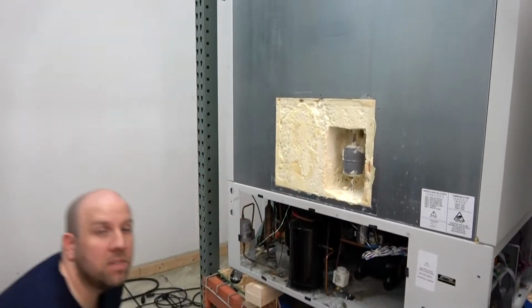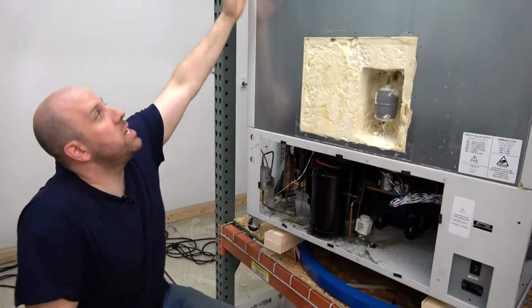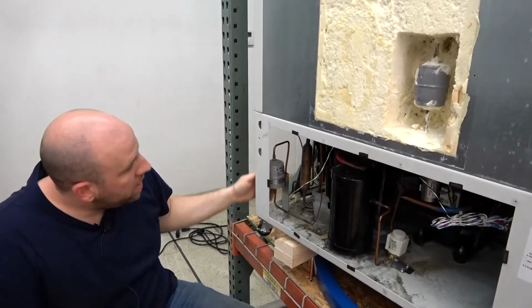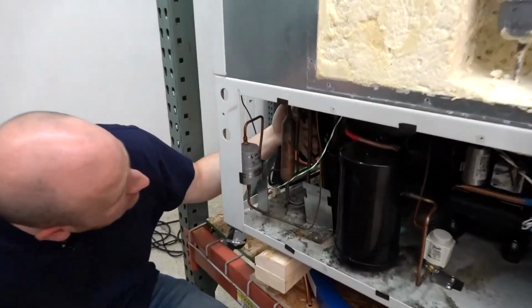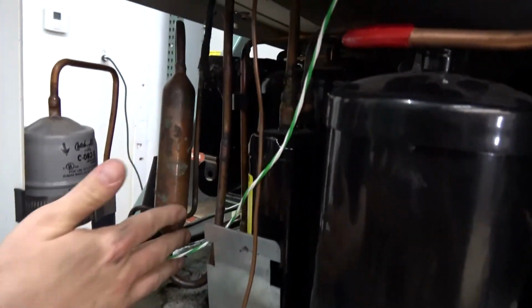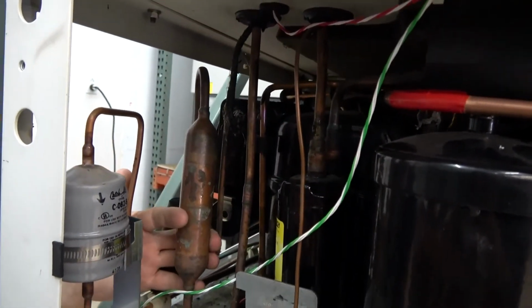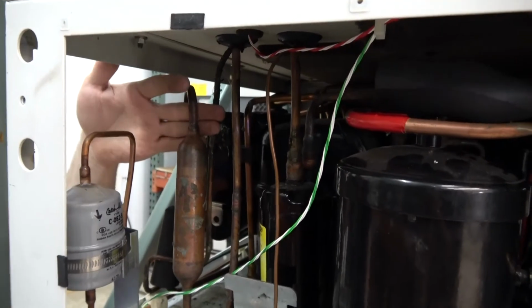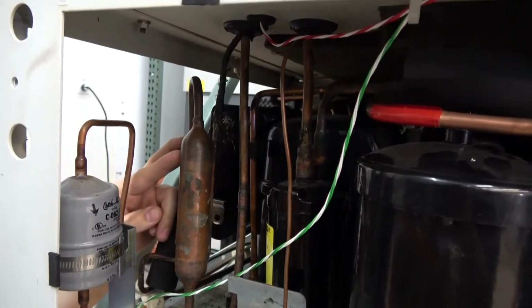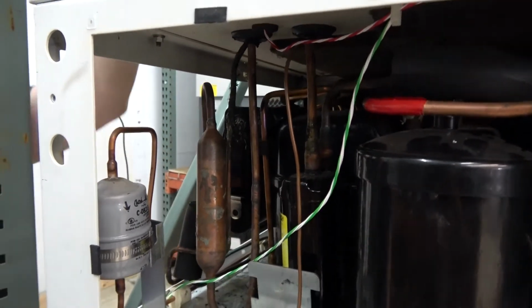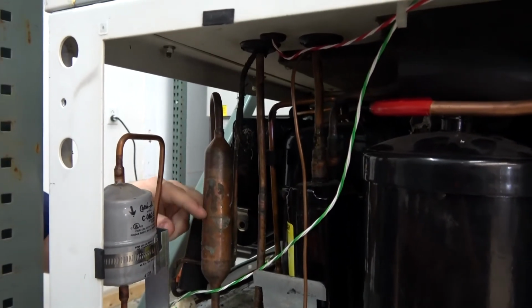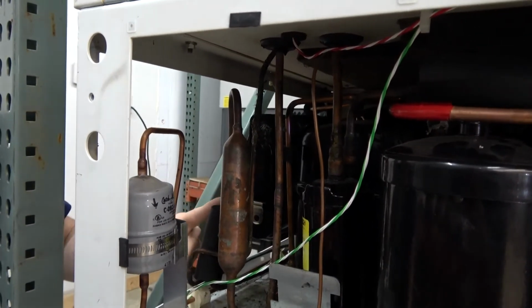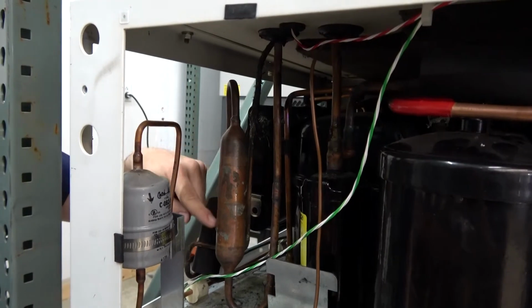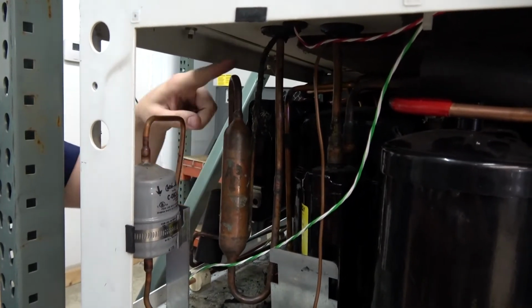So after it's done cooling off and taking all the heat out of the inside, it comes back down through this line. And once again, this is kind of like a liquid trap. So in case there's any liquid refrigerant that got through and didn't evaporate up here where it was supposed to, this will kind of trap it. And the gas will continue on through back to the compressor, but this liquid will sit here until it evaporates, and then it'll come back through.